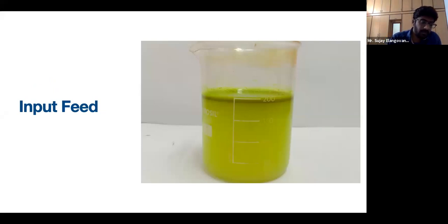Traditionally, the industries were disposing of the penetrant water through an authorized agent, as there was no specific method available to treat it on site. Evaporation is the technology to treat this, but the traditional evaporators were very costly, as the quantity generated wouldn't be greater than 5 KLD or 5,000 liters a day, and they require a boiler and cooling tower. Now we have energy efficient, compact, electricity based vacuum evaporators, which can treat process water from 0.25 KLD itself.